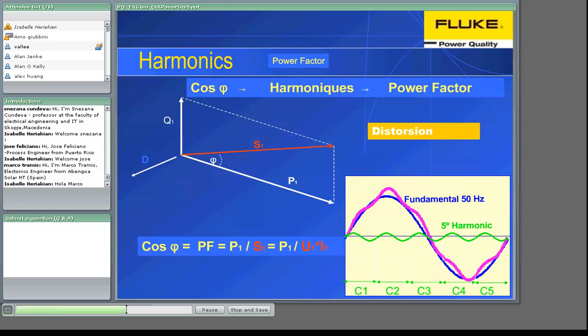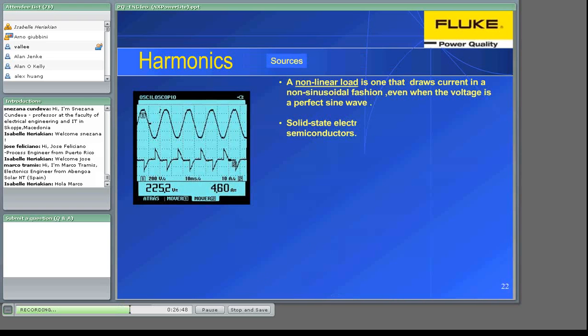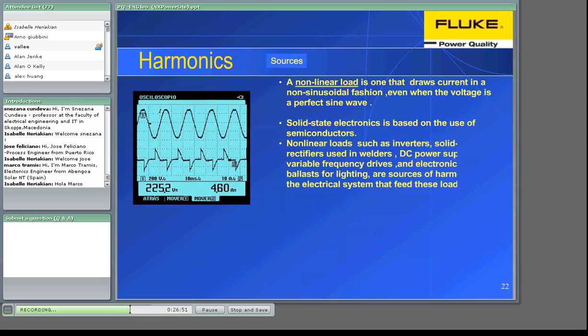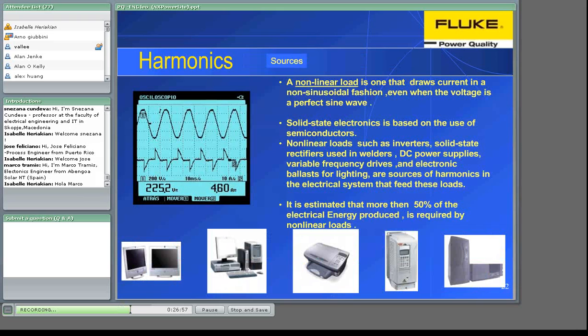Let's carry on. Sources of harmonics. In the early days of power supply design, the common single-phase power supply was linear. Nowadays, every electronic machine, PC, printers, copy machines, is using a switched mode DC power supply. The advantages are reduced power losses and reduced size and weight of inductive components like transformers. You can imagine the advantages in, for instance, aeronautics applications. The drawback consists in the generation of harmonics.